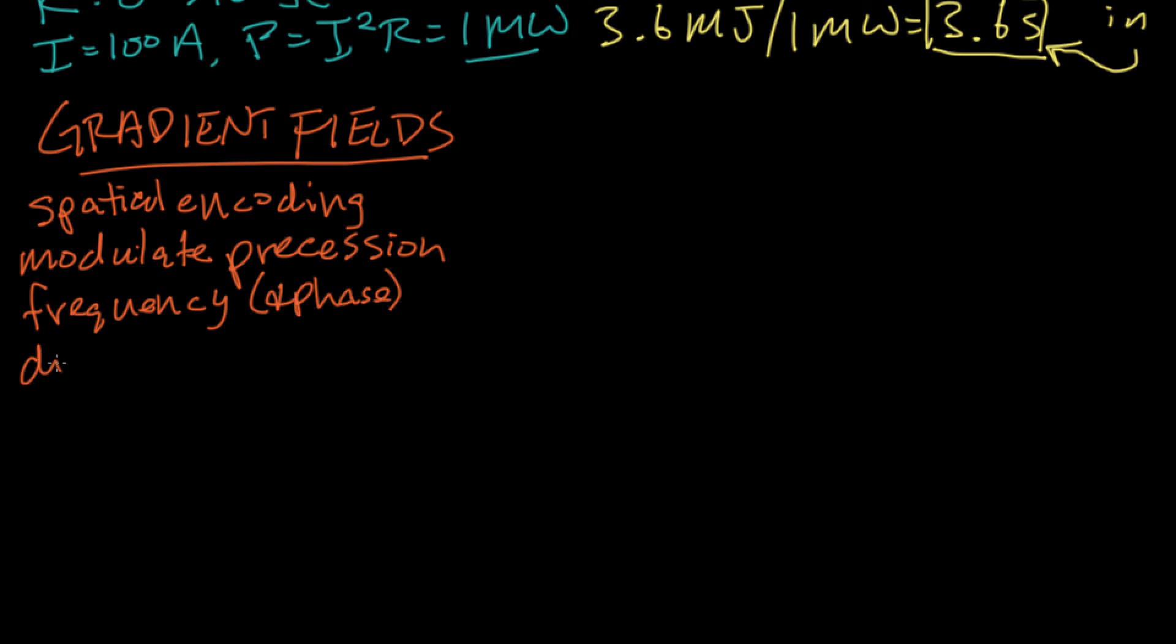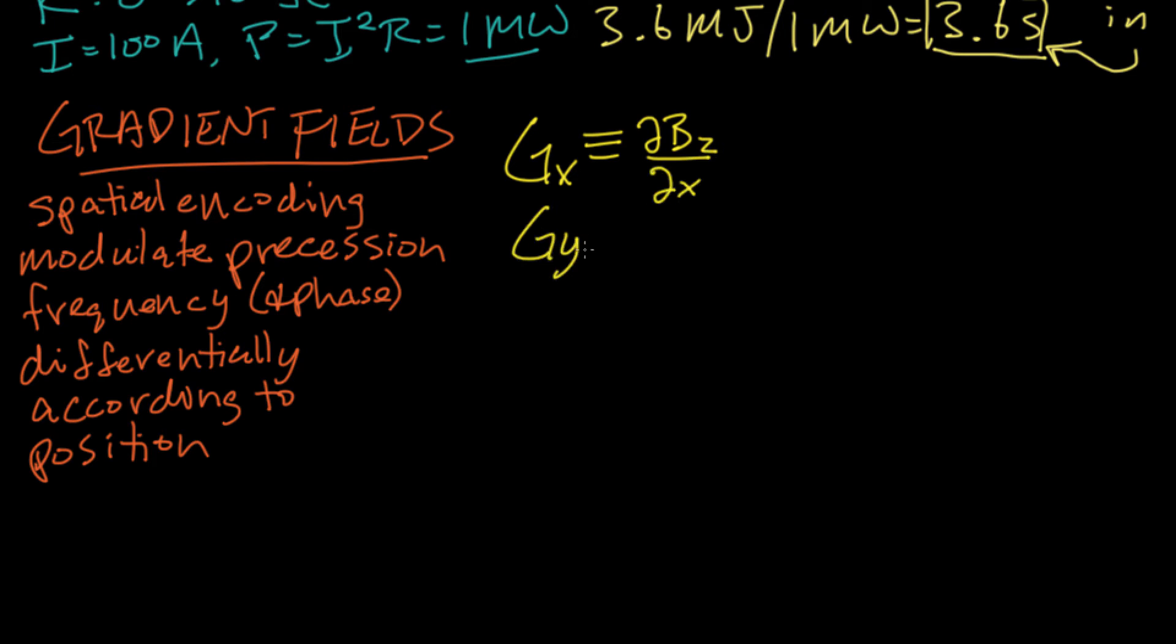Okay, now moving on to gradient fields. The job of the gradient fields are to provide spatial encoding. They do that by modulating the precession frequency, and therefore phase of spins, differentially or according to position. There are three independently controlled gradient coils and sets of gradient fields. Each of the gradient axes is characterized by the partial derivative of the z component of the field with respect to their coordinate. And the reason that the z component of the field is what matters is as follows.